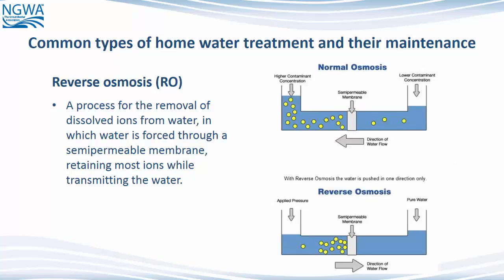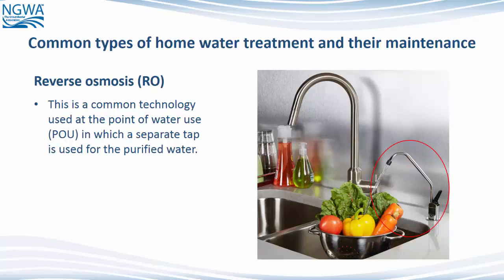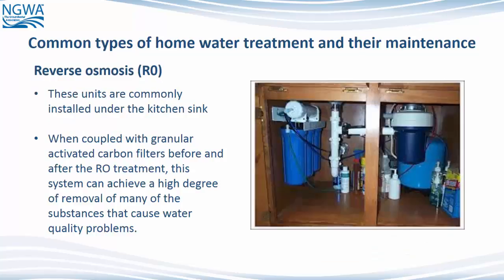Next, reverse osmosis or RO. This is a process for the removal of dissolved ions from water, in which water is forced through a semi-permeable membrane, retaining most ions while transmitting the water. This is a common technology used at the point of water use, or POU, in which a separate tap is used for the purified water. These units are commonly installed under the kitchen sink. When coupled with granular activated carbon filters before and after the RO treatment, this system can achieve a high degree of removal of many of the substances that cause water quality problems.